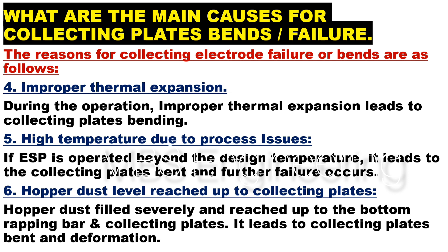Hopper dust level reached up to collecting plates. Hopper dust filled severely and reached up to the bottom rapping bar and collecting plates. It leads to collecting plates bending and deformation.